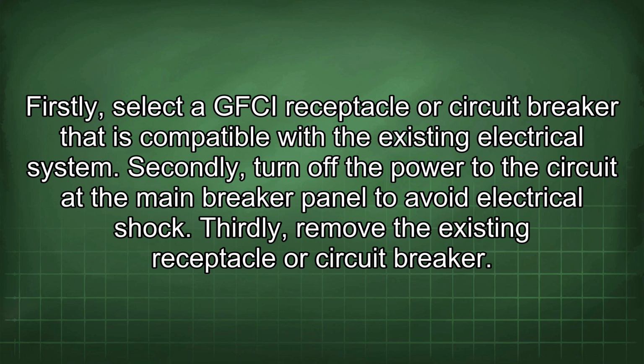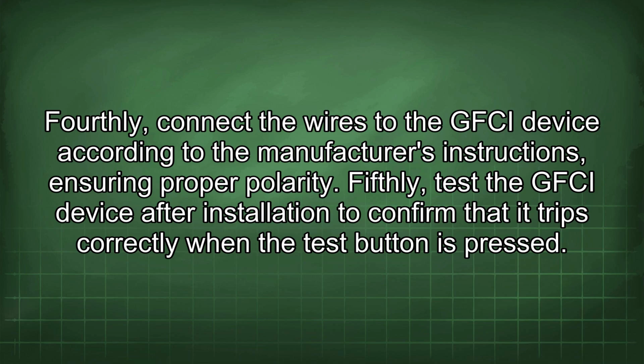Thirdly, remove the existing receptacle or circuit breaker. Fourthly, connect the wires to the GFCI device according to the manufacturer's instructions, ensuring proper polarity. Fifthly, test the GFCI device after installation to confirm that it trips correctly when the test button is pressed.